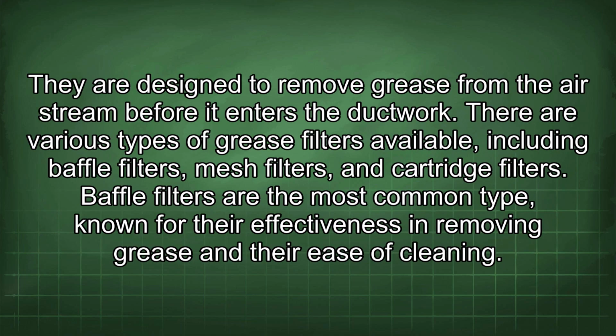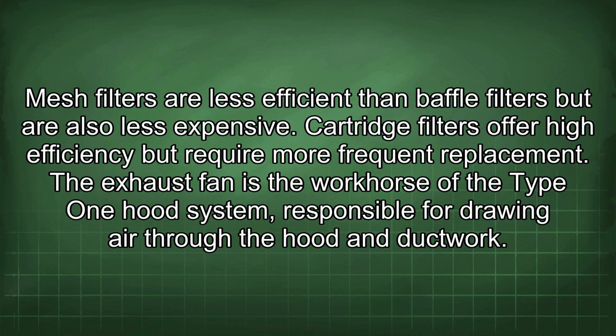They are designed to remove grease from the airstream before it enters the ductwork. There are various types of grease filters available, including baffle filters, mesh filters, and cartridge filters. Baffle filters are the most common type, known for their effectiveness in removing grease and their ease of cleaning. Mesh filters are less efficient than baffle filters but are also less expensive. Cartridge filters offer high efficiency but require more frequent replacement.